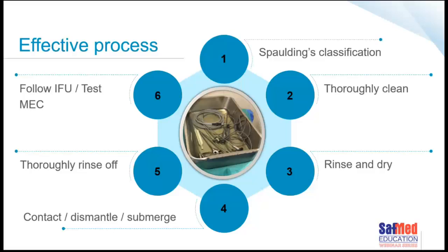So important to dismantle the devices that you can. If there are lumens, you need to make sure that the disinfectant is being placed or flushed through the lumen itself, and that the contact time that the device has with the high-level disinfectant is as per the manufacturer's instructions for use. If it says 5 minutes, well, then it takes at least 5 minutes to reduce the microorganisms to that 5 or 6 or 4 log reduction that is required. And you need to soak it for that amount of time.